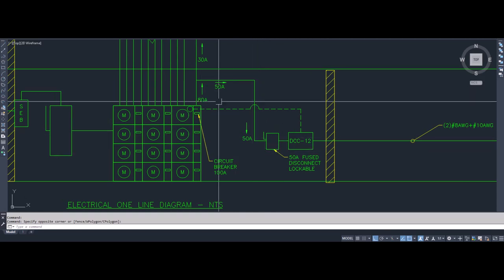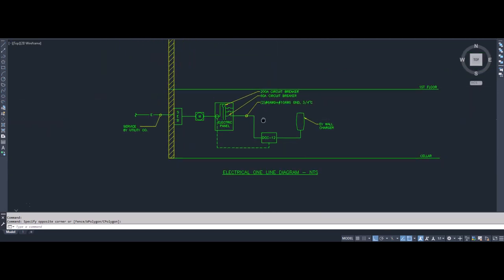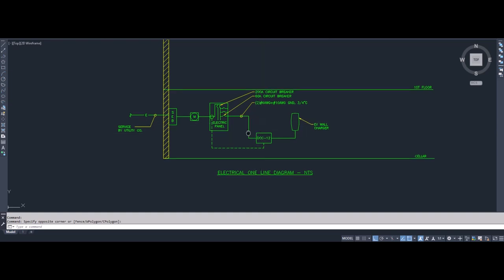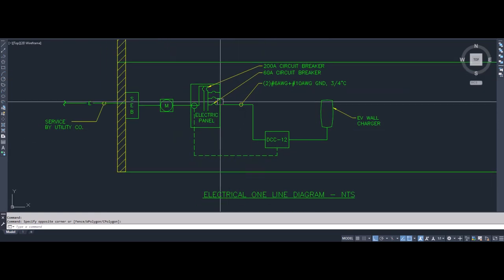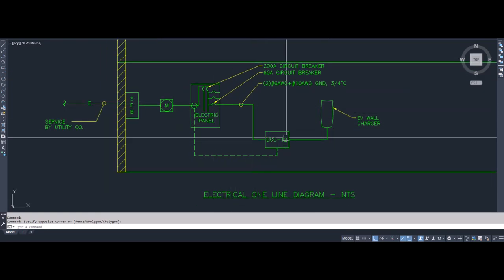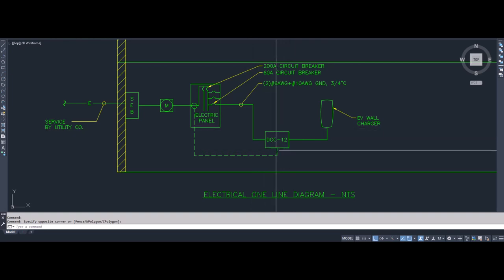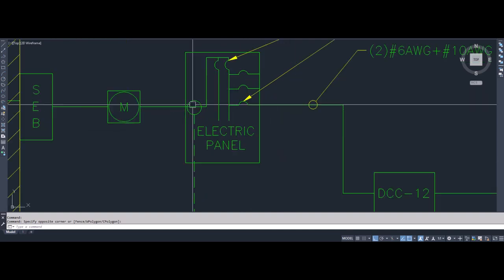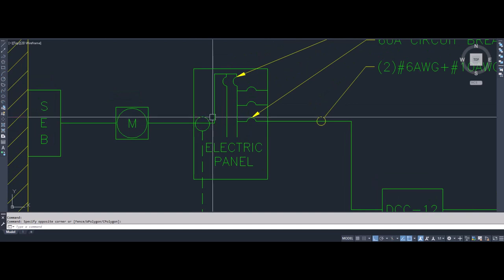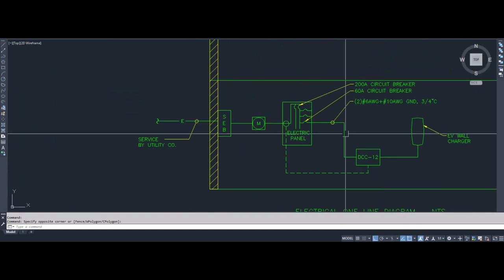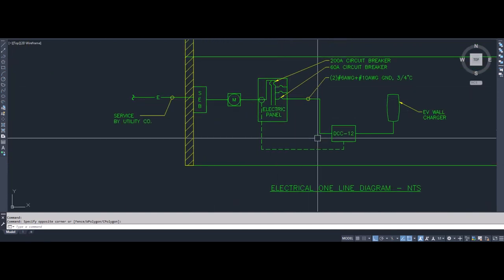such as drawn here. So in this case, for a simple one-family home, everything is kind of close. So you could use this breaker to feed your DCC12, and then your remote current transformer should go right on the main before it splits to your main loads and your EV load. So this is one way.